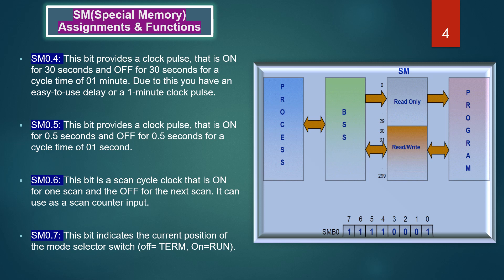SM 0.7: this bit indicates the current position of the mode selector switch — off equals term, on equals run. This bit can be used to enable freely programmable communication when the switch is in run, and you can enable normal communication with the programming device by setting the switch to term.